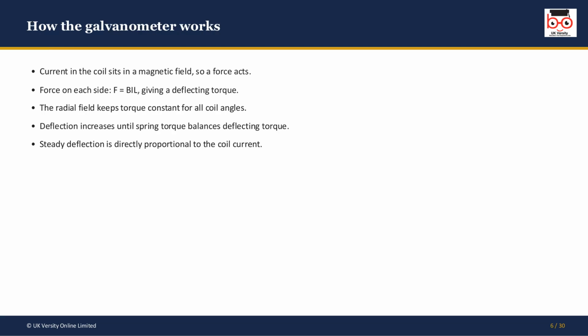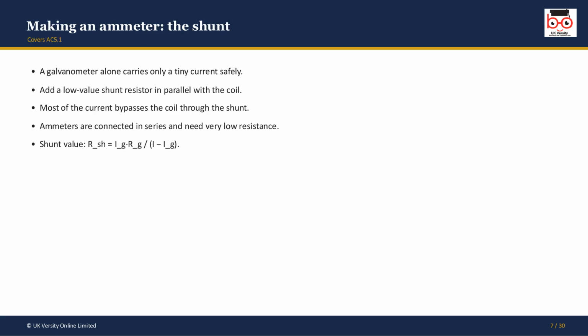So how does it actually work? The current in the coil sits in a magnetic field, so a force acts on it, force equals BIL on each side, and together these give a deflecting torque. That clever radial field keeps the torque constant whatever angle the coil turns to. The coil deflects until the spring's restoring torque exactly balances the deflecting torque. And because of that balance, the steady deflection ends up directly proportional to the current, which is what makes the scale easy to read. On its own, a galvanometer can only carry a tiny current safely.